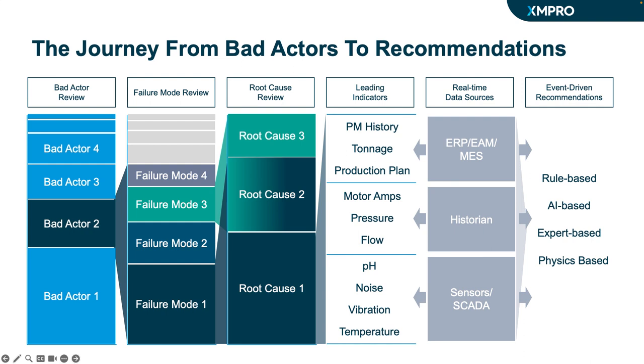So now that we understand what the root causes are, this is really the bread and butter of a lot of maintenance organizations, the work that we see being done right now. So understanding what the root causes are, and then looking for what are the lead indicators for that root cause. Is it the planned maintenance history, the tonnage, the motor amps, the vibration, the flow, whatever the lead indicators are, and from what systems do we need to bring them, so that we can create these rules, either rule-based, AI-based, the person who's been there 30 years, and also applying some engineering calculations, because most of the things that we do still subscribe to the laws of physics, so we can use our engineering calculations to do that. So that's just some of the approach that we take.